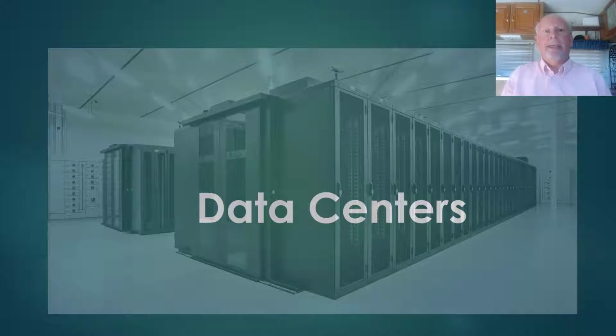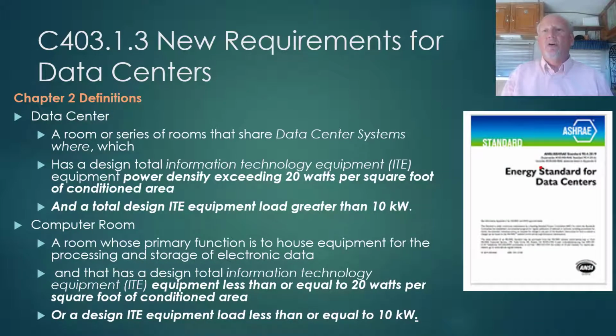So let's get into our mechanical portion here with data centers. The Washington State Energy Code has adopted ASHRAE standard 90.4 for the HVAC system efficiency of systems serving data centers. So the first thing we need to start with is what's a data center. New definitions have been added to the code. So if you're trying to determine if your computer room or computer rooms are considered a data center or not, you need to refer to the definition.